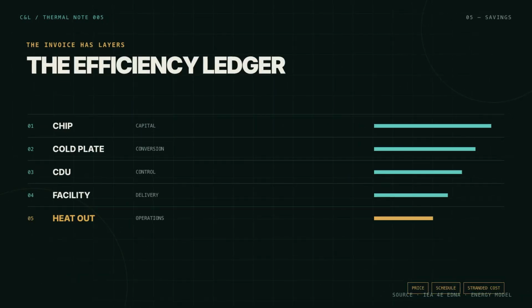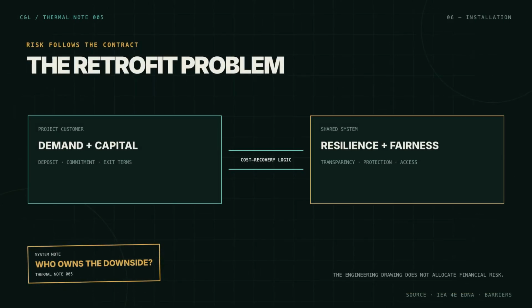The EDNA report estimates that liquid cooling can cut server energy use by up to 8% by reducing fan power. At the facility level, it can lower cooling-related energy use by roughly 30 to 40%, producing overall data center savings in the order of 10 to 21% depending on deployment and design. Those are system estimates, not guarantees for every site. Climate, supply temperature, heat rejection, workload, and existing equipment all matter. Still, the logic is powerful. Every watt not spent moving heat can support additional compute or reduce the electrical and cooling capacity required for the same output.